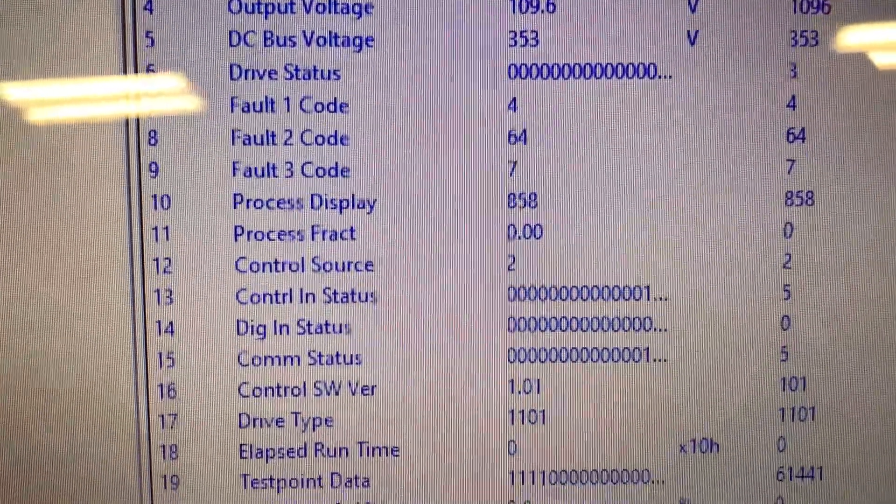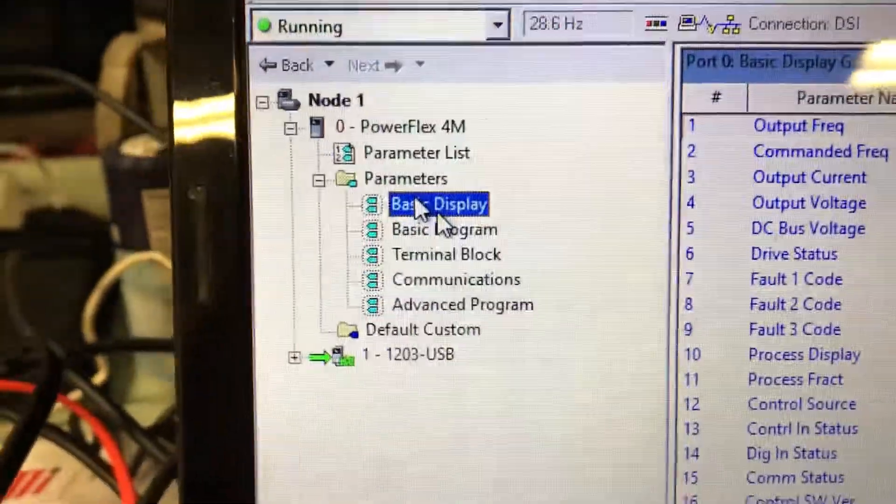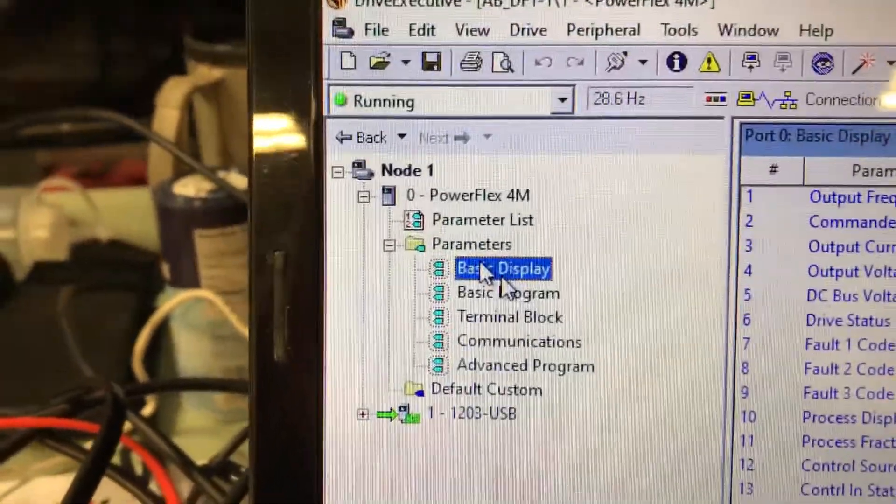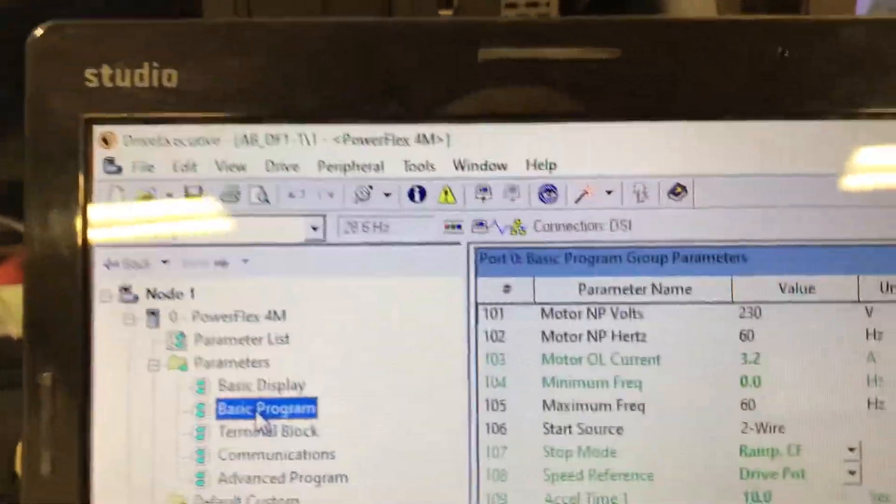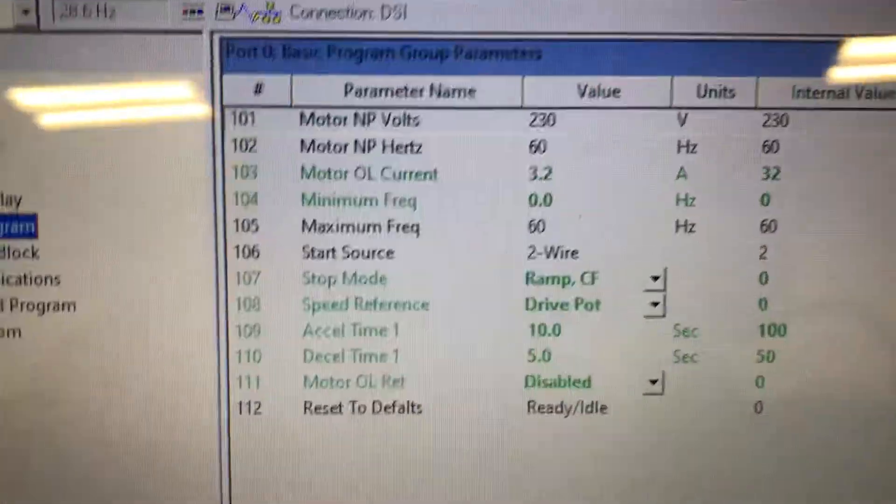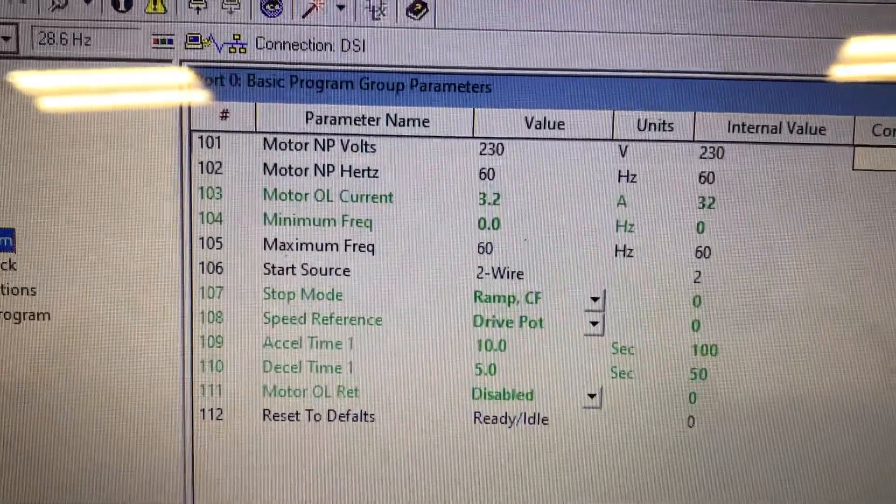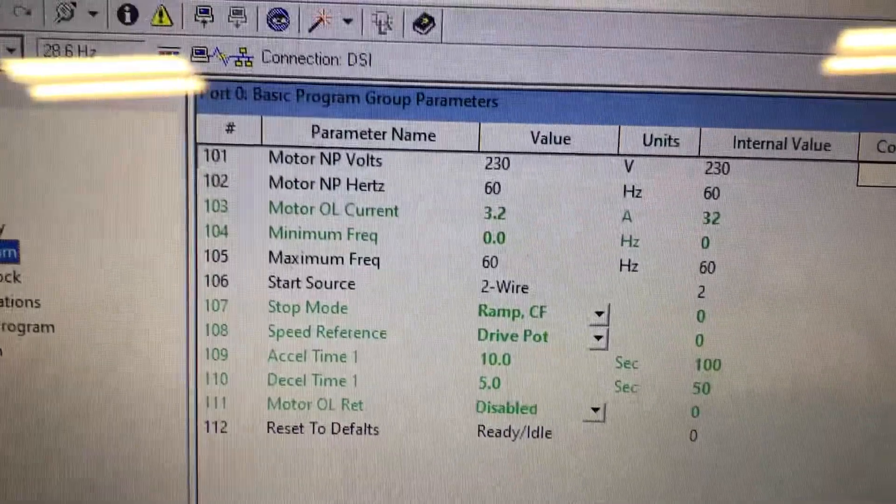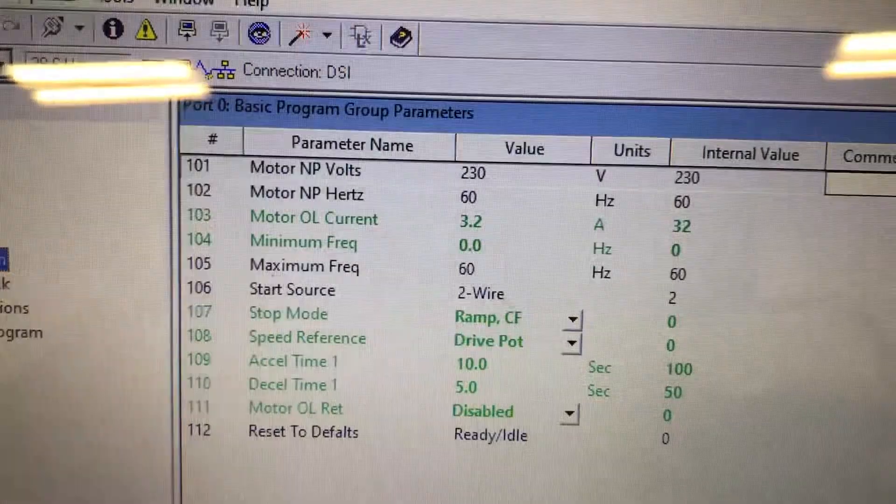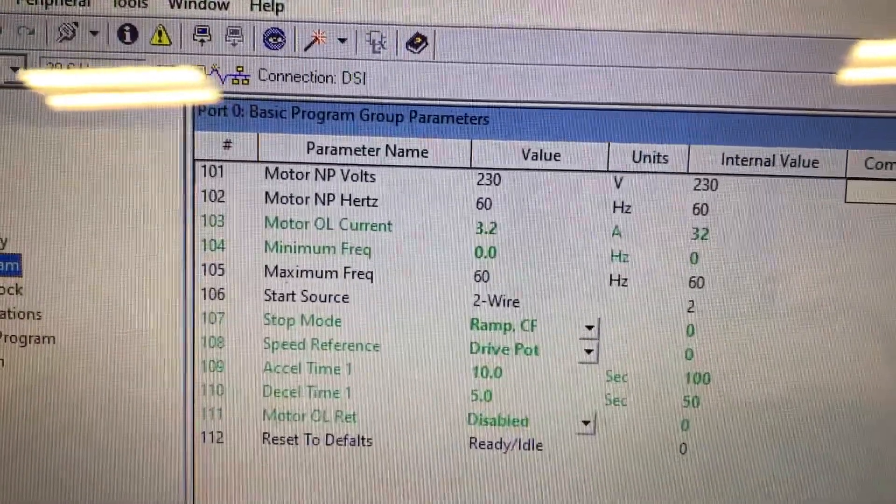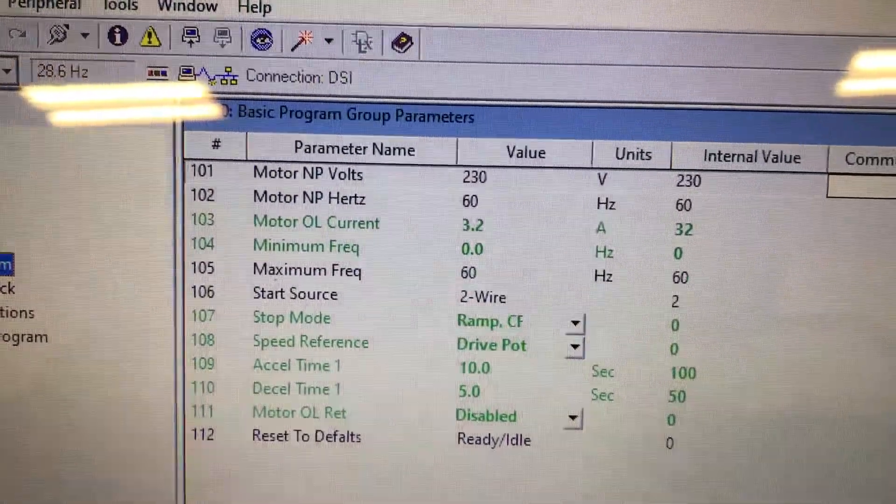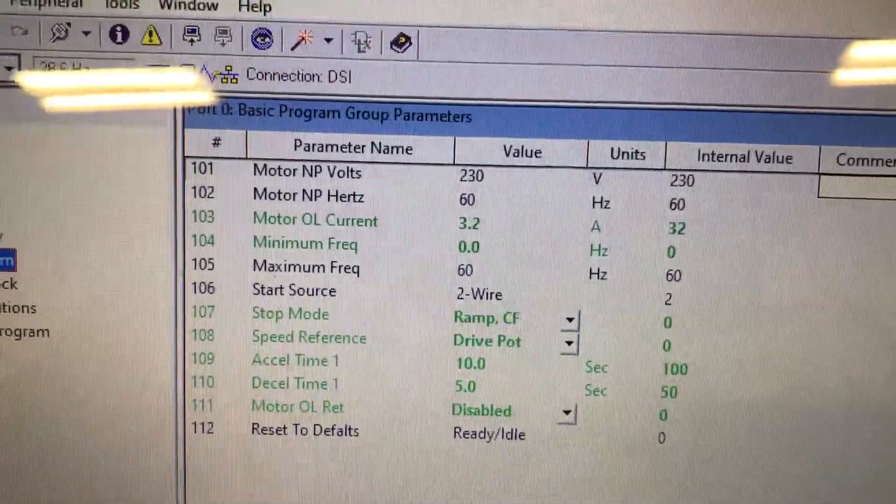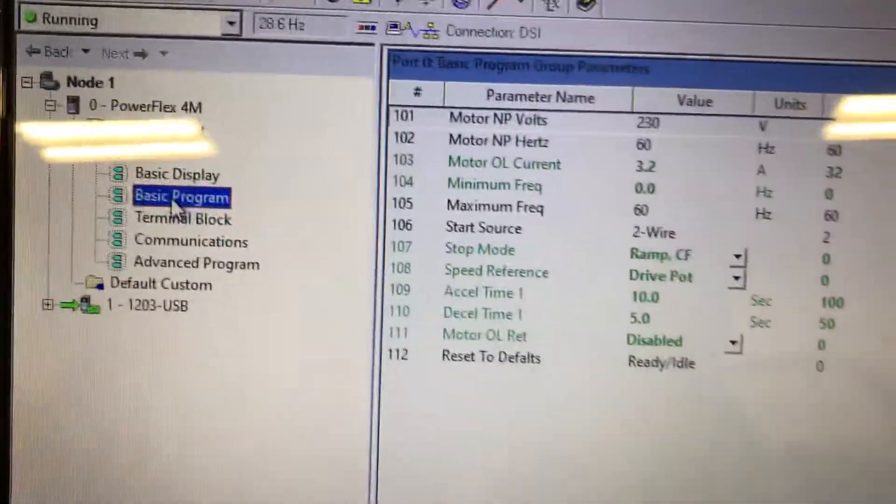Here is our basic programming. Notice our input is 230, 60 Hertz, 3.2 amps, minimum frequency zero, start source, all that stuff. Our accel time is 10 seconds, and our decel time is 5. So when you hit the stop button, it should decel in less time.